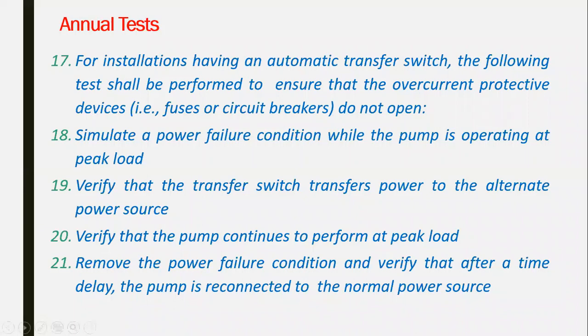Normally, the pump is fed from the normal power of the electrical system, and it is working at rated capacity and peak load. If the power coming from the normal source is disconnected, the ATS has to transfer within a maximum of 10 seconds, transferring the connection from the transformer to the generator. And the generator has to work at full capacity within a maximum of 10 seconds and feed the pump. So this transfer from the normal source, which failed and which we simulated as a failure, to the generator is within 10 seconds.